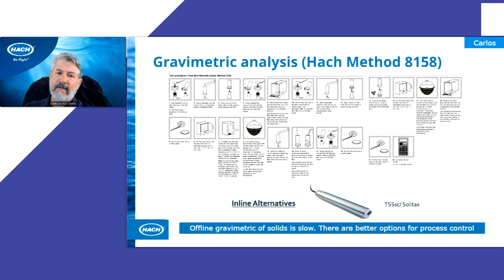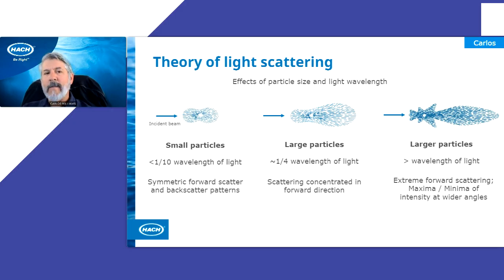So an inline alternative that folks are going to talk a lot more about is a TSS SC or a Solitax. This is a probe you can use to measure online. A little bit about the theory of light scattering. When we use a nephelometer, one of the key components is something that measures at 90 degrees. What these images are showing you is when light scatters at 90 degrees, over here on the far left side, you get a pretty equal distribution of light scatter. At least it's equal in these two lobes you see on either side. Then as you move to different means of scattering, or as the particles get larger and larger, or both, you start seeing very strange patterns of light scatter, which is why a lot of the TSS measuring technologies will have within them at least one detector that measures at 90 degrees, and then depending on the instrument that you're using, may have more than that.